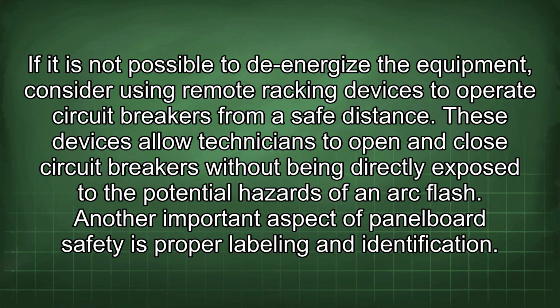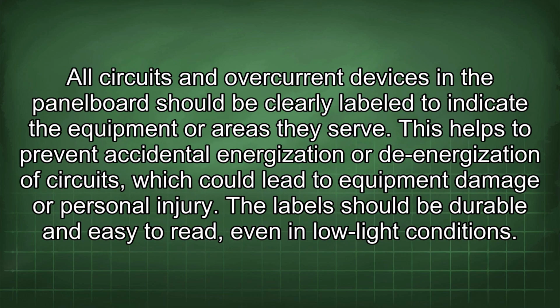of an arc flash. Another important aspect of panel board safety is proper labeling and identification. All circuits and overcurrent devices in the panel board should be clearly labeled to indicate the equipment or areas they serve. This helps to prevent accidental energization or de-energization of circuits, which could lead to equipment damage or personal injury. The label should be durable and easy to read, even in low light conditions.